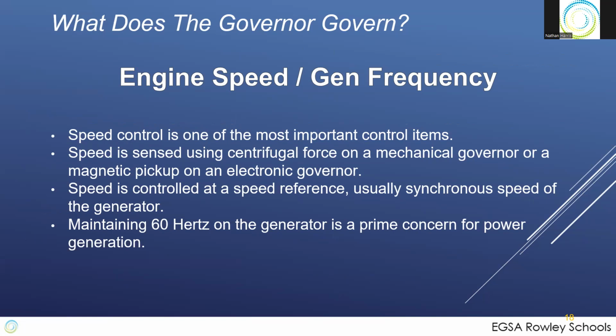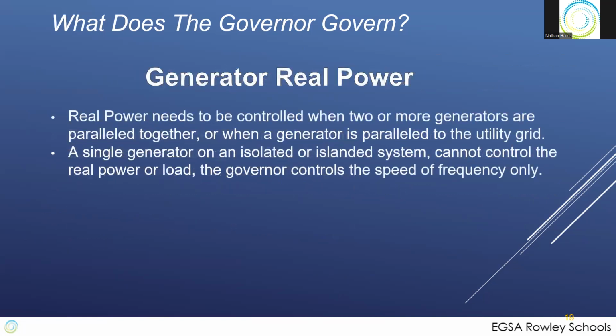Centrifugal force is sometimes used in the old mechanical governors, and today it's a digital system. And of course, you're trying to maintain 60 hertz. The governor also regulates real power when it's parallel with utility. Single gen or parallel gens on an island system, the governor controls the speed and the frequency only.